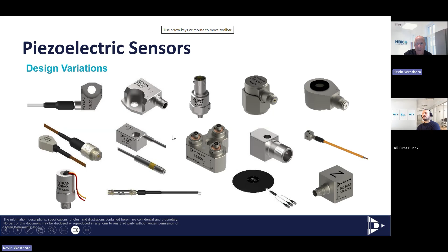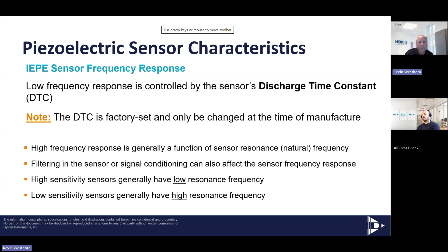We put the DTC, the discharge time constant, on the data sheet of the accelerometer, but the easiest way to determine what your low end frequency is, is just to look at the data sheet and look at the specification for frequency. We always give you the low end frequency and the upper frequency, and that would dictate what the discharge time constant is. Okay. And so let's just go ahead and show you what a typical output of an IEPE accelerometer looks like up here in the upper graph here.